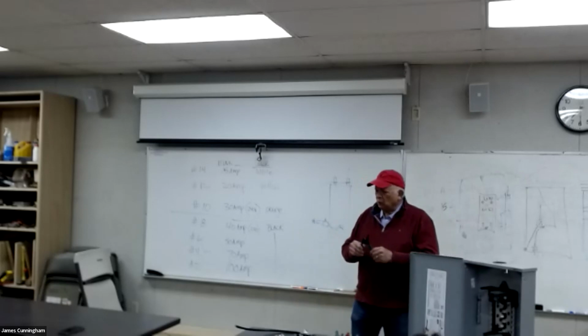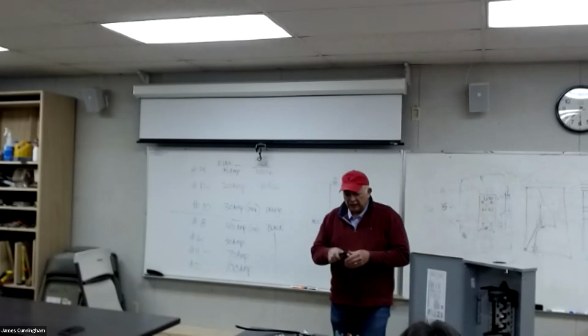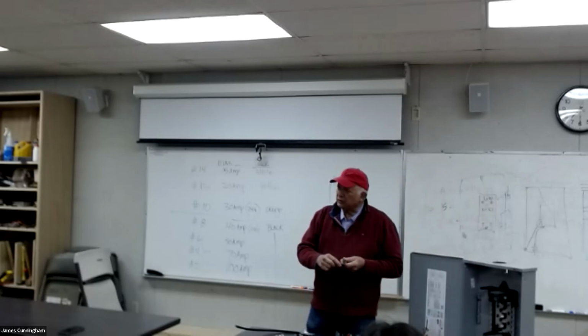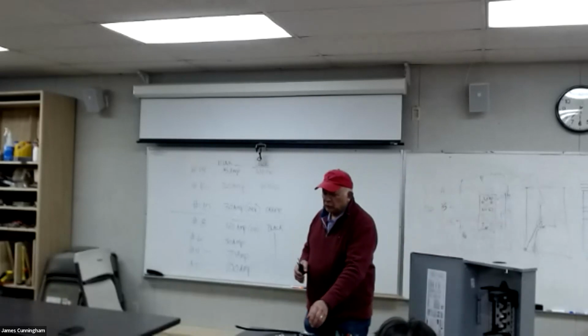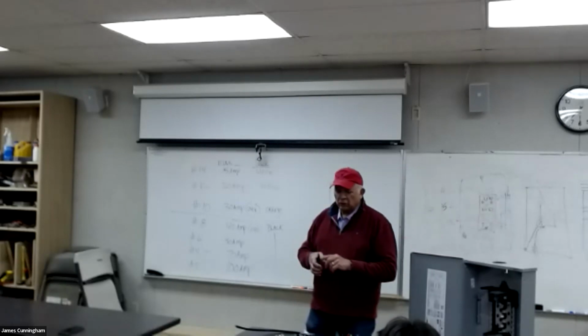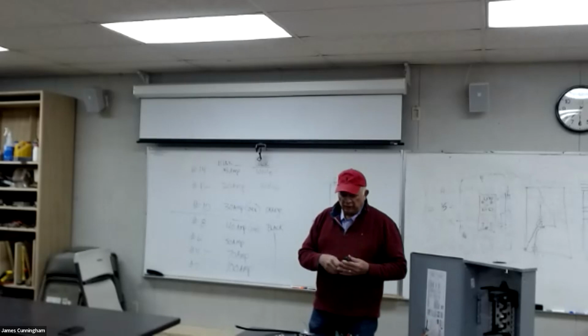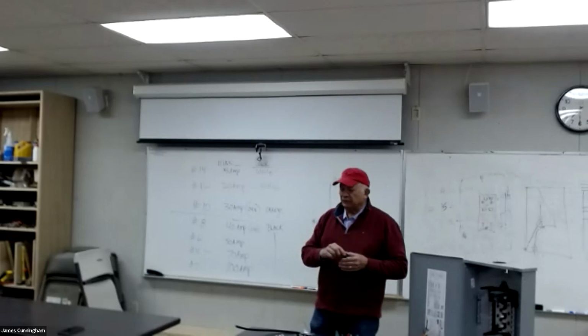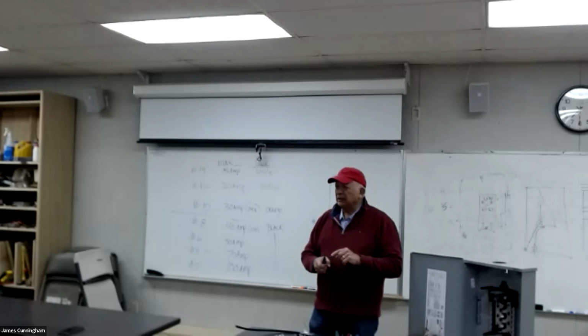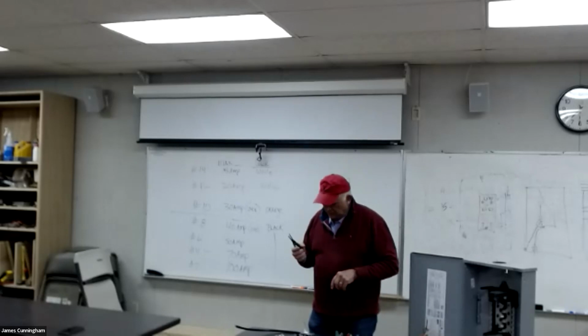So when we're doing the wiring installation, we have wire strippers, and on the wire strippers, they have numbers. The numbers stand for the sizes of wire. You don't want to use the wrong number for the wrong size wire, because you can partially cut it, and then it becomes a weak point and the wire will break off or something like that. So if I'm doing a number 14 wire, I want to make sure I'm using the 3rd slot from the bottom here. That's going to be number 14 wire. Number 12 is the second, number 10 is the bottom. And then as you go up, it gets smaller and smaller wires, but the biggest one is number 10 on these. The biggest size wire.